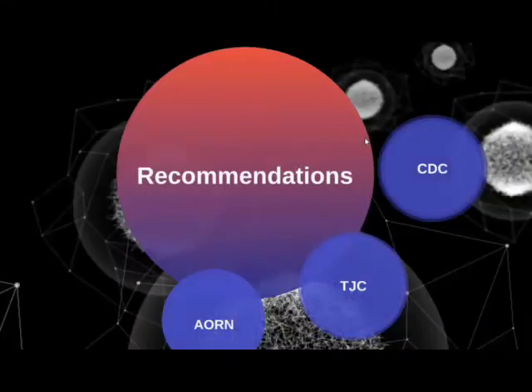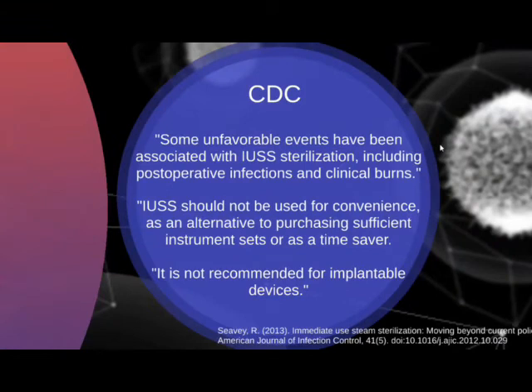Recommendations from the Centers for Disease Control, the Joint Commission, and AORN, also known as the Association of Operating Room Nurses. So the CDC says some unfavorable events have been associated with IUSS sterilization, including postoperative infections and clinical burns. IUSS should not be used for convenience as an alternative to purchasing sufficient instrument sets or as a time saver. It is not recommended for implantable devices.